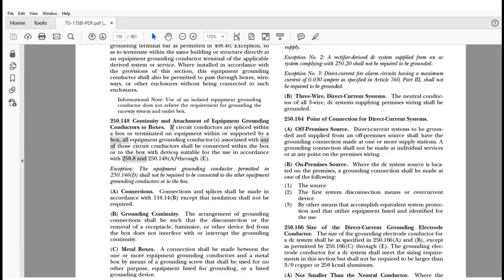And I would say, look, the whole purpose of the system, the whole purpose of tying it together to create that low impedance fault current path is to connect the system together so that we have that one path. So the code here is saying, look, it doesn't matter whether it's a 14 gauge or a 12 gauge, if they're in the same box, they have to come together to create that system. That's what it's saying here.